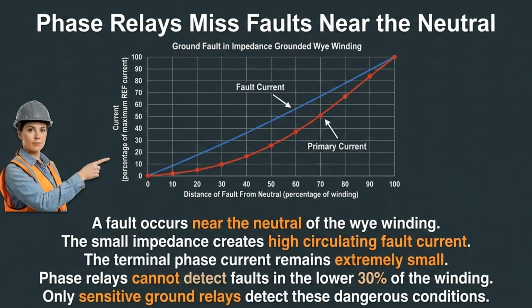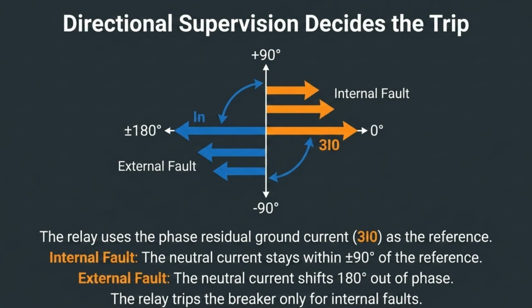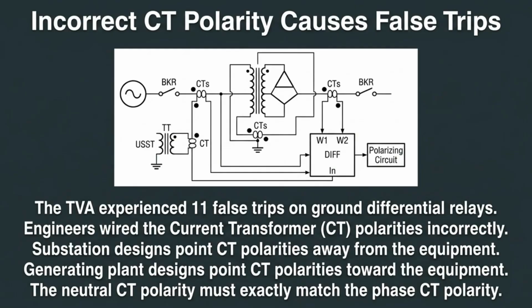Faults occurring near the neutral of a Y winding are notoriously difficult to detect. Because phase current remains low, standard relays often fail. Sensitive ground relaying is required to monitor these specific conditions. Directional supervision is key to preventing incorrect trips. By using the residual ground current as a reference, the relay can distinguish between internal and external faults, tripping only when necessary. Correct polarity is crucial.